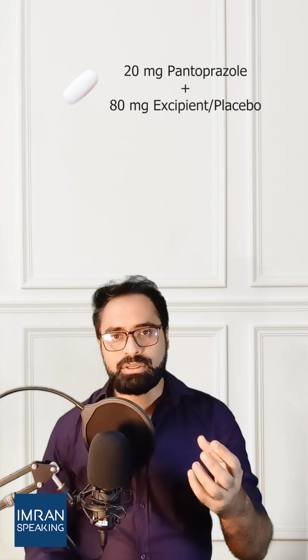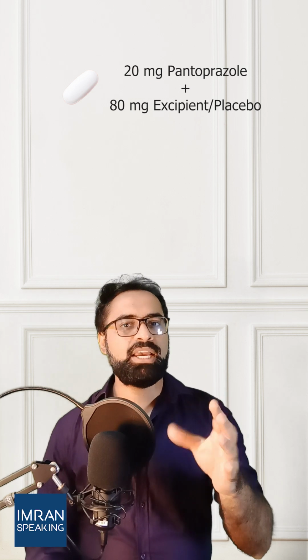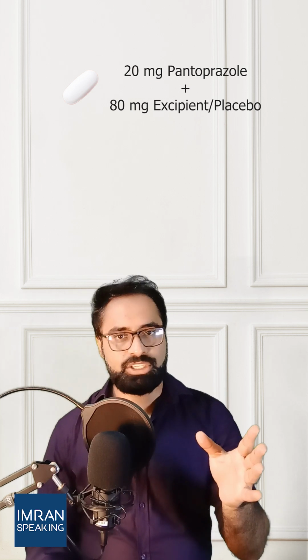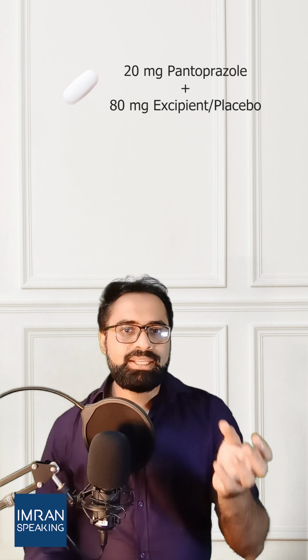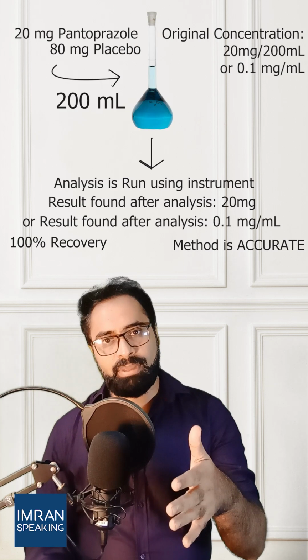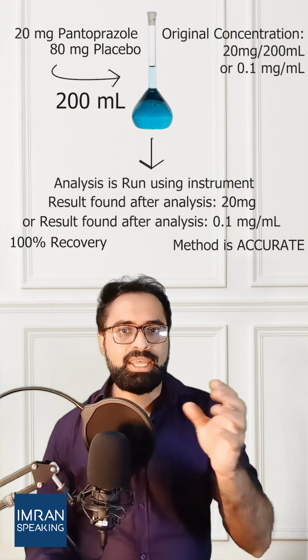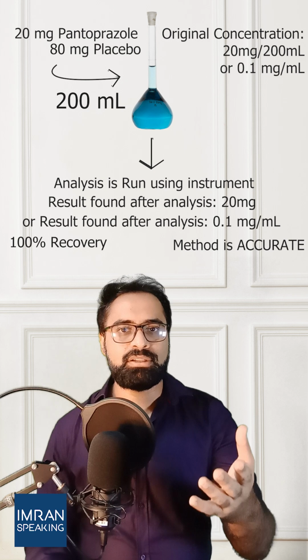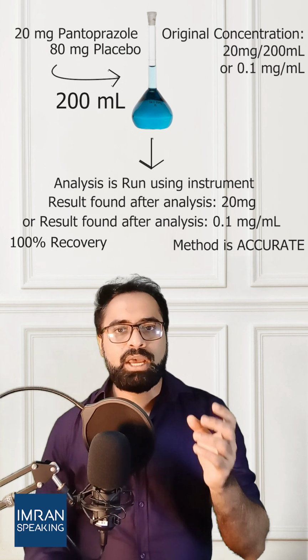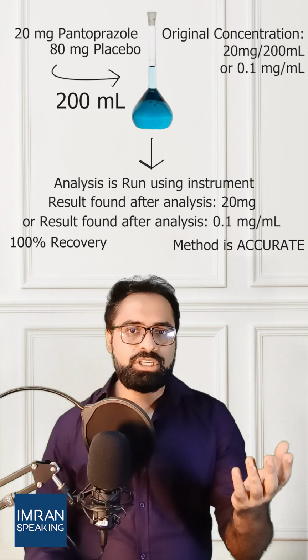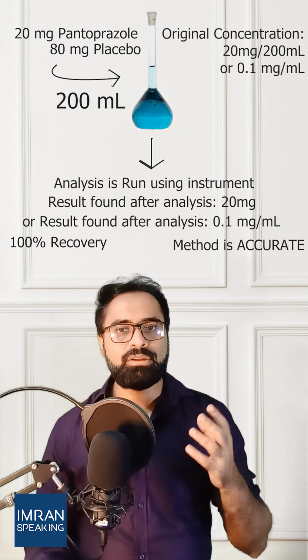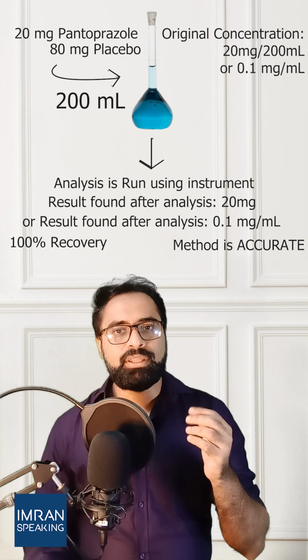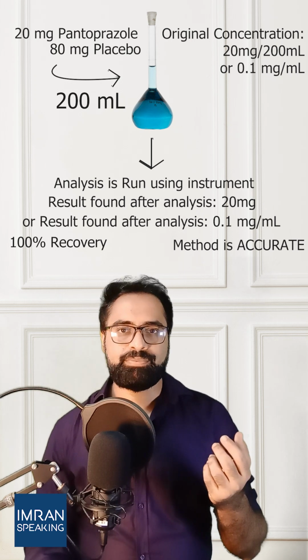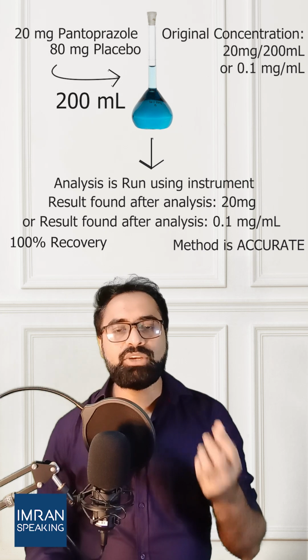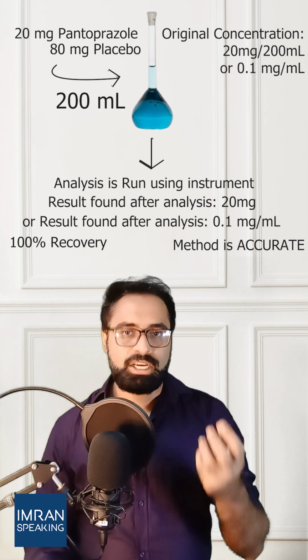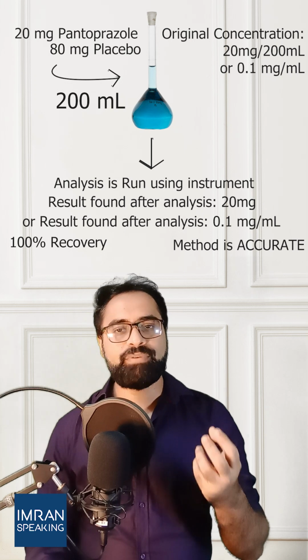Suppose we have a tablet which has 20 milligram of API and 80 milligram of excipients in it. Now, we make the sample by weighing 20 milligram of API and 80 milligram of placebo in the lab and make the analytical solution as per the method. Now, after analysis, the quantity of API we get from calculation is 20 milligram. Then percent recovery will be 100%. Hence, we can say that the method is accurate as the method can detect and quantify the quantity of API correctly.